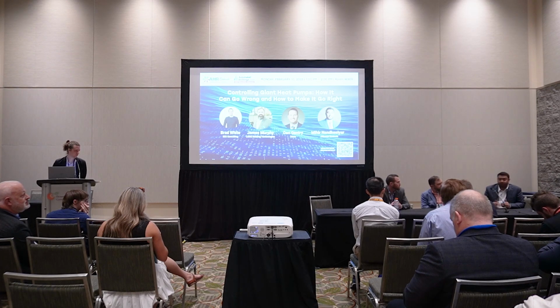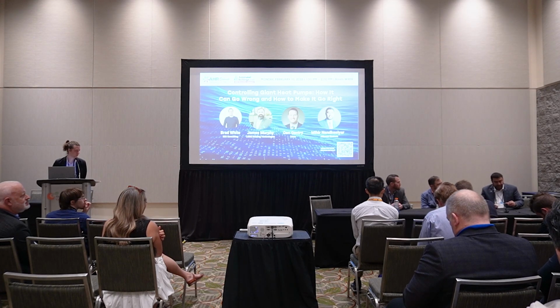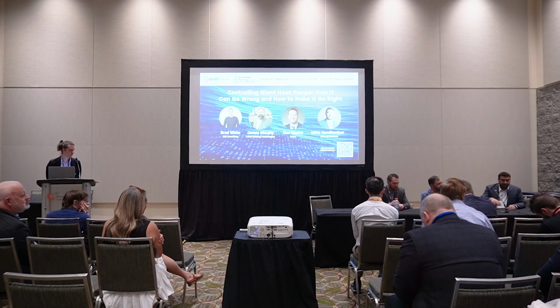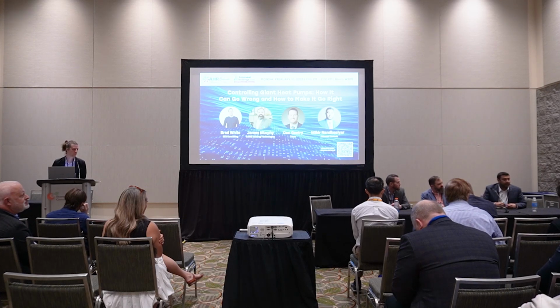If you know what that is, knowing the load profile is great because there's no rule that says you have to buy 50-ton chillers or 50 million BTU, there are 5 million BTU blocks, right? You can buy or you can design in a 1 million and a 9 million BTU boiler or a heat pump. You can design in multiple different sizes that allow you to utilize the plant space, but hit your low loads, hit your efficiency targets, hit your year-round operation points that you're seeking to hit while you're decarbonizing.